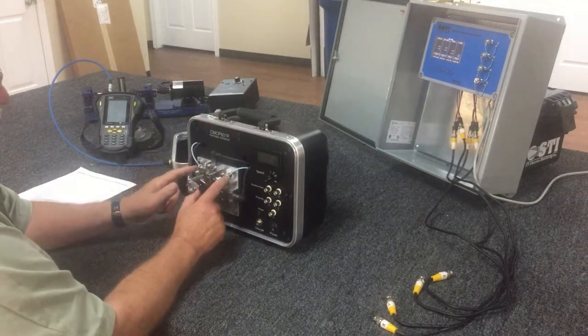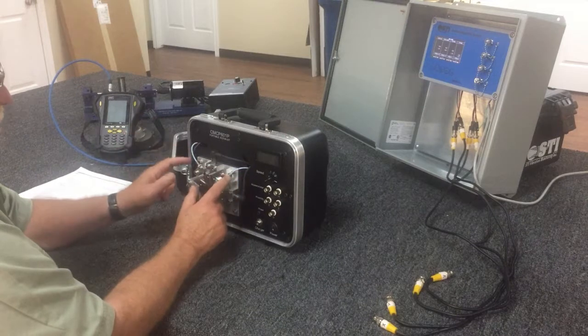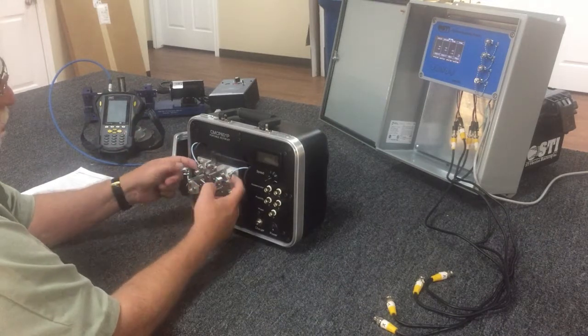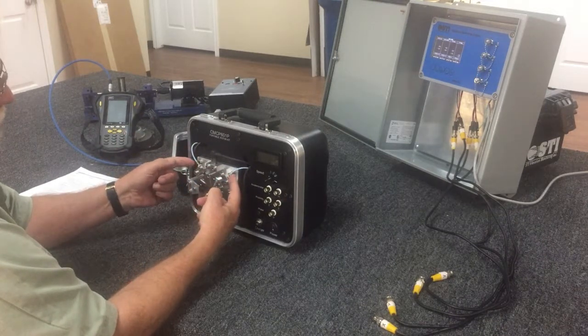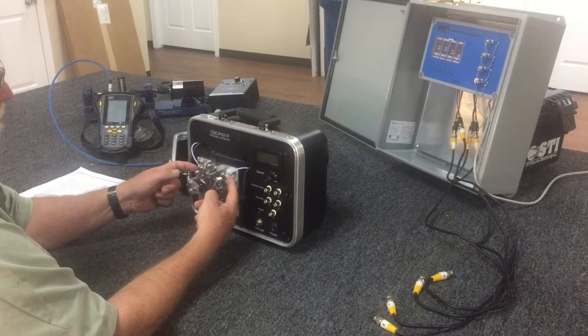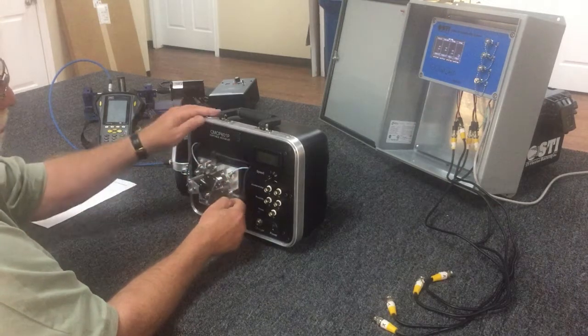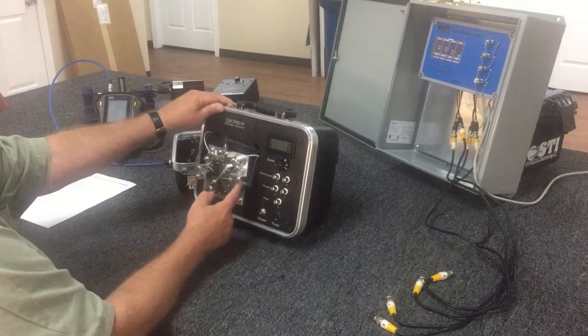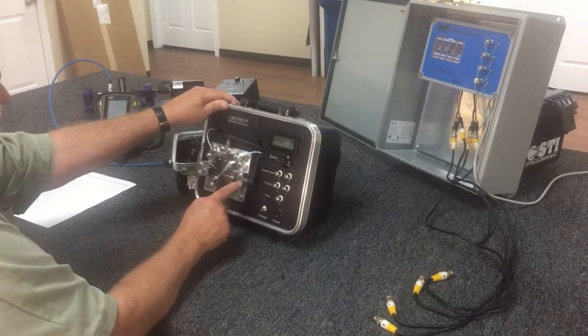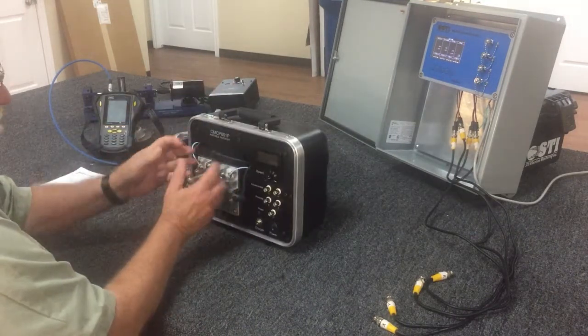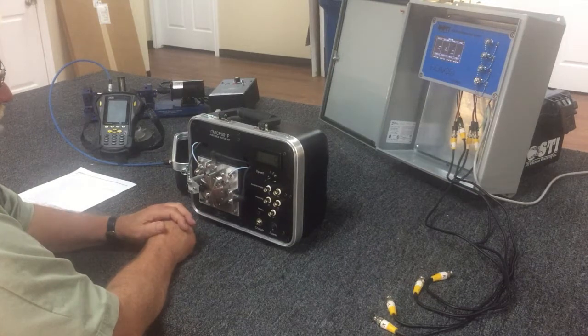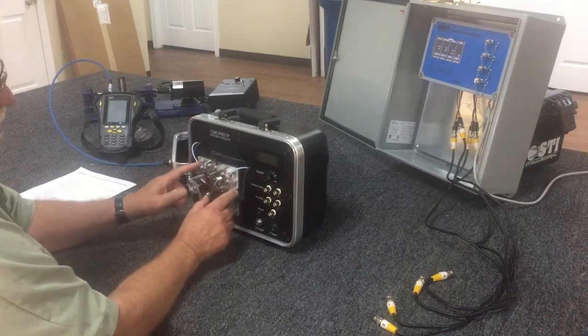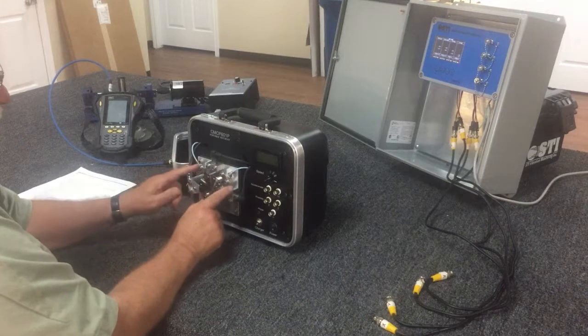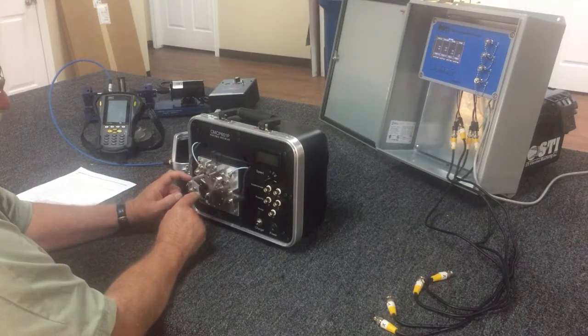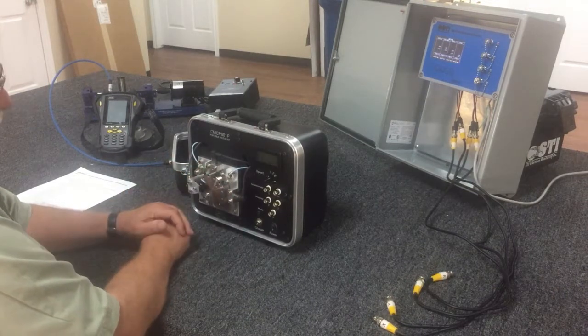We have X and Y blocks that we normally use for proximity probes, but they're 1/4-28 threaded, so you can either mount a proximity probe in them or you can mount accelerometers on them. Then we have vertical and horizontal that are 1/4-28 mounted in the same type of block. So basically you can mix these sensors up any way you want to. The standard unit does not come with sensors. It comes with the mounting blocks, comes with the phase probe, and you mount your own sensors.